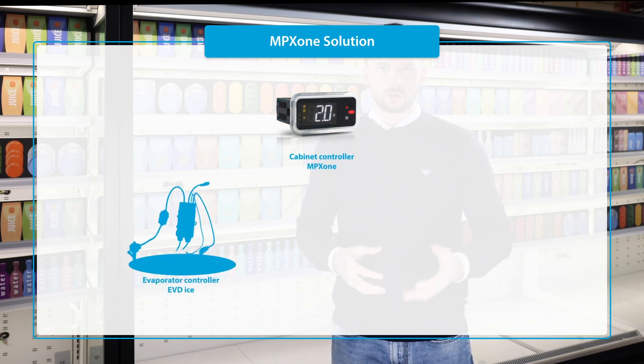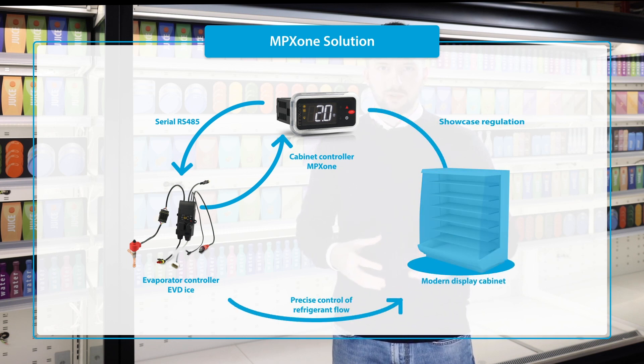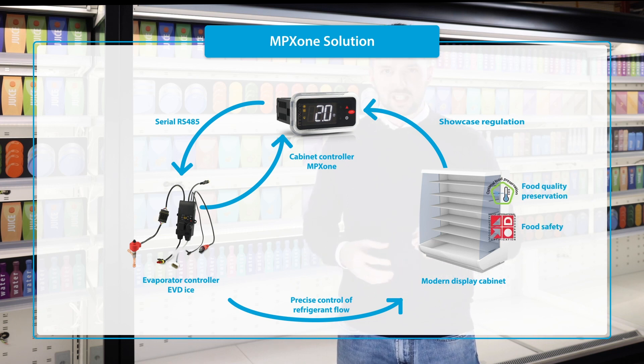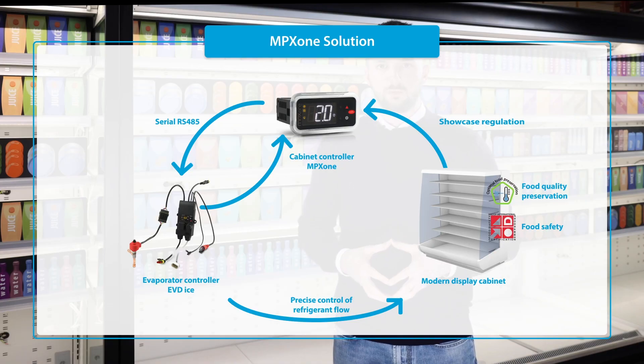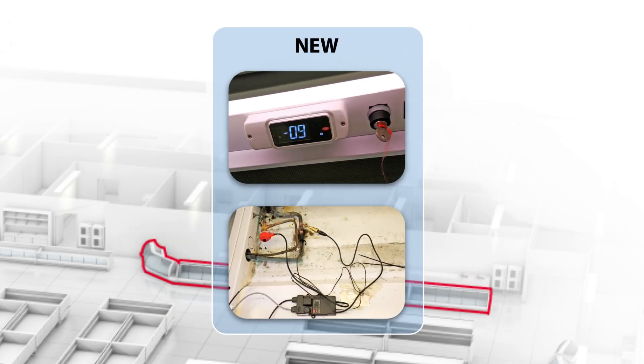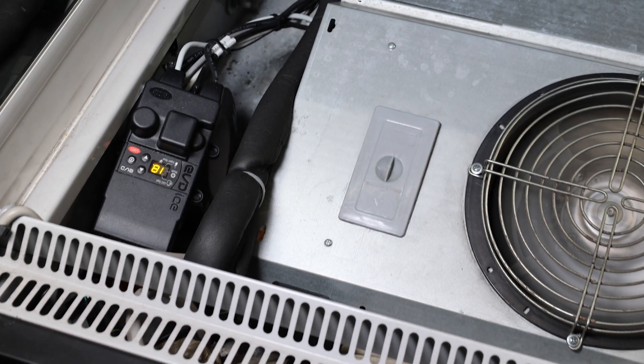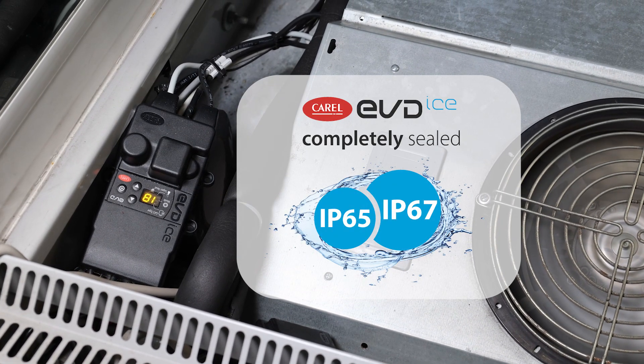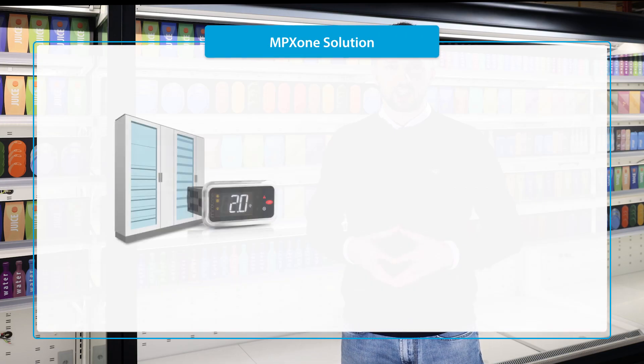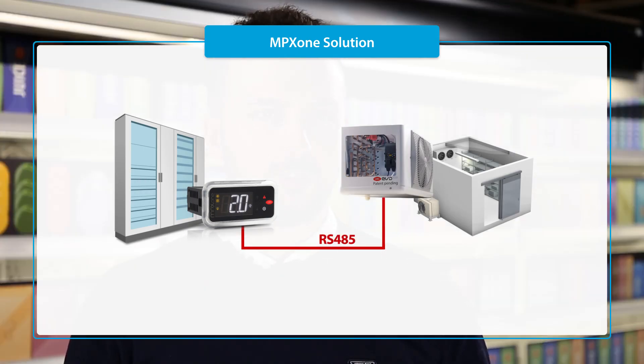Complete integration between the cabinet controller MPXone and the evaporator controller EVD ice via serial communication on one hand allows the unit's appearance to be renovated with a modern display, and on the other improves the quality of food preservation thanks to precise control of refrigerant flow. This integration is ideal for both retrofit installation where a simple procedure is needed and where there are space restrictions in the electrical panel, as the EVD ice's valve driver can work in critical environmental conditions, meaning it can be installed directly in the evaporator compartment, and for new installations where there are large distances between the electrical panel and the evaporator, exploiting the RS485 serial connection.